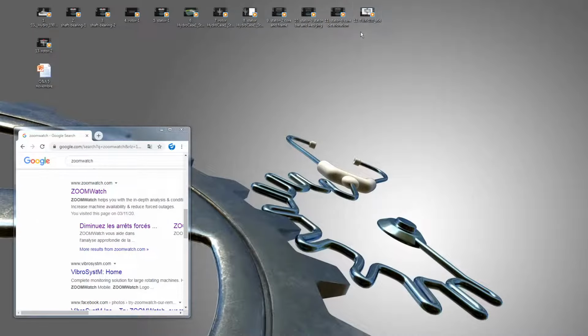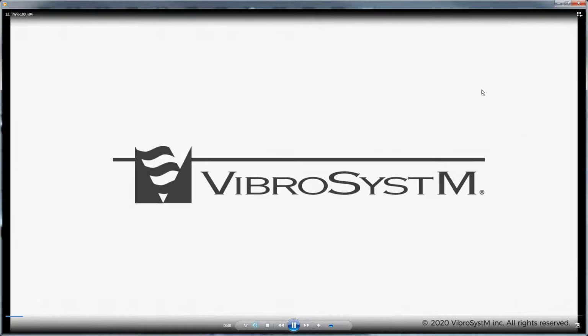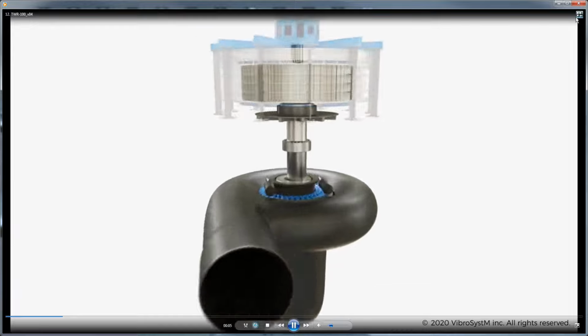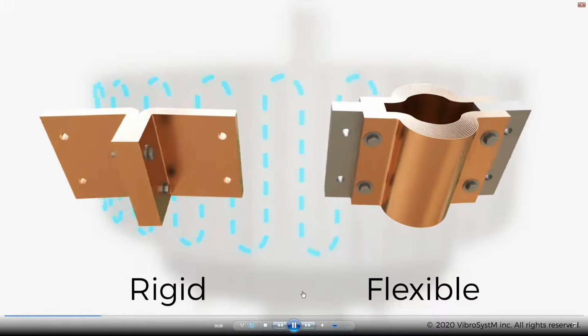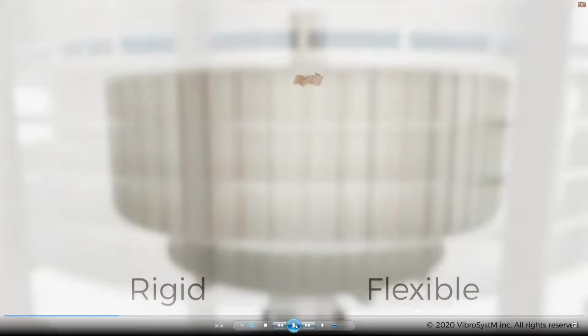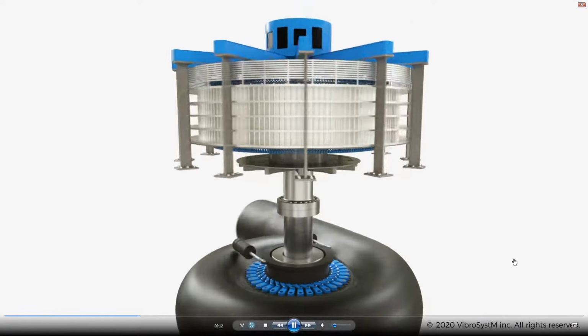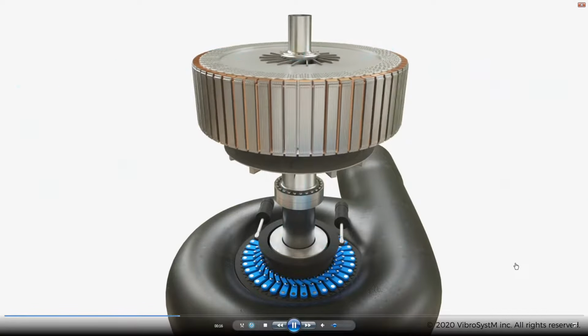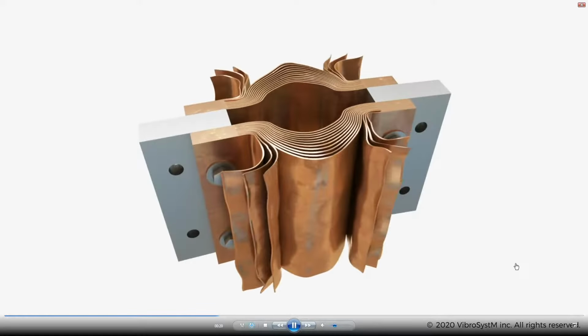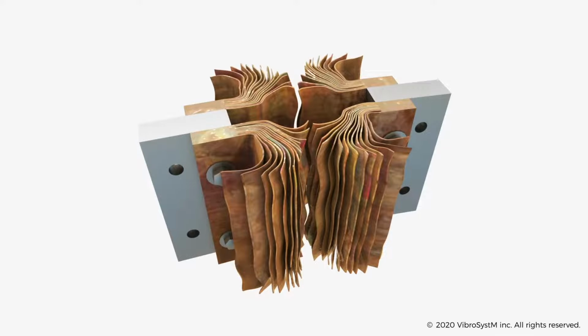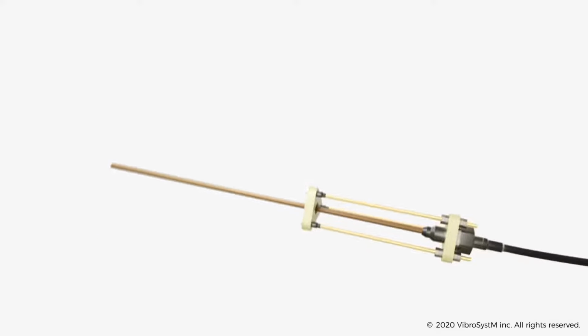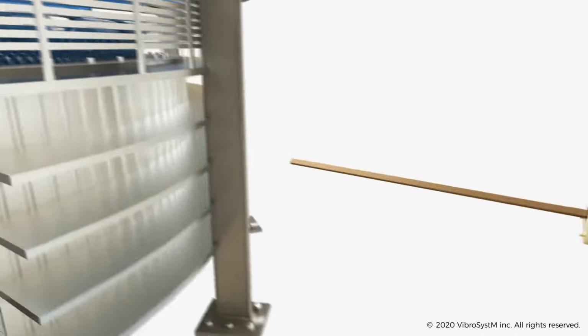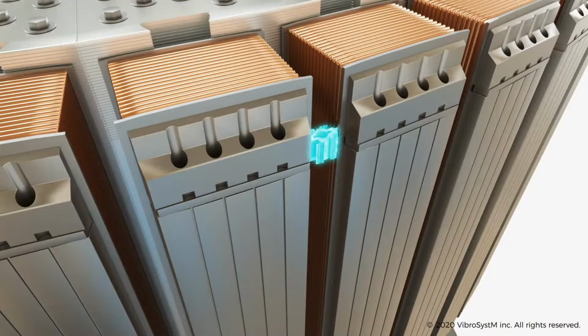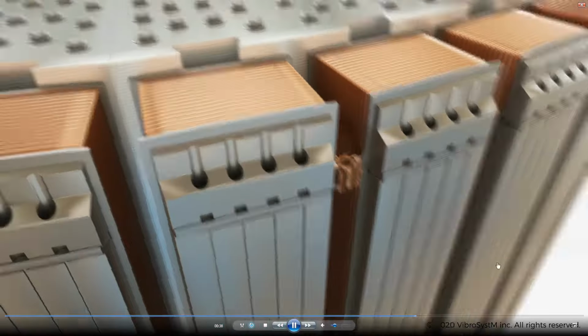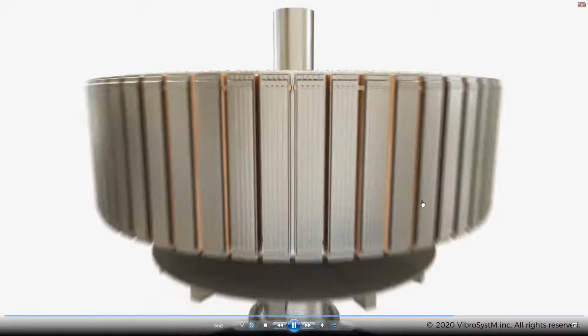All right, so let me show you a small video I wanted to show you about the ThermaWatch rotor. Okay, you can see two types of connections. Of course, there are different models, but there's two standard types, the rigid or the flexible. And again, repeated cycling, centrifugal forces, heating, expansion, contraction can lead to failure of these interconnections. And it might be a better idea to be able to measure the temperature and detect hot rotor pole joints and replace them before they fail and cause damage, rather than instead of doing it during an outage, just replacing it and preventing damage to the unit per se.